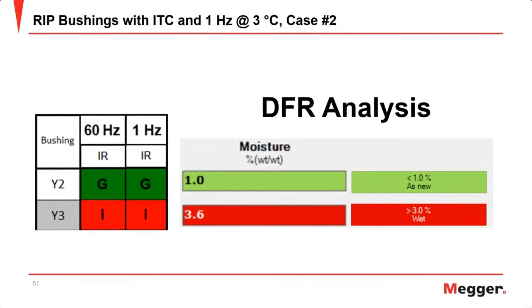And absolutely what they found with these RIP bushings is that they tested the bushing that was good at 60 and 1 Hertz and saw that the moisture was as new. And then for that bushing that had the torn wrapping with the water inside touching the bushing, it certainly had high moisture. So when you think about the different tests and how you can really make the most of the technology that's available today, it's important to consider that really 3-step process of testing insulation at 10 kV 60 Hertz, 1 Hertz, and then DFR to pinpoint where the issues are.